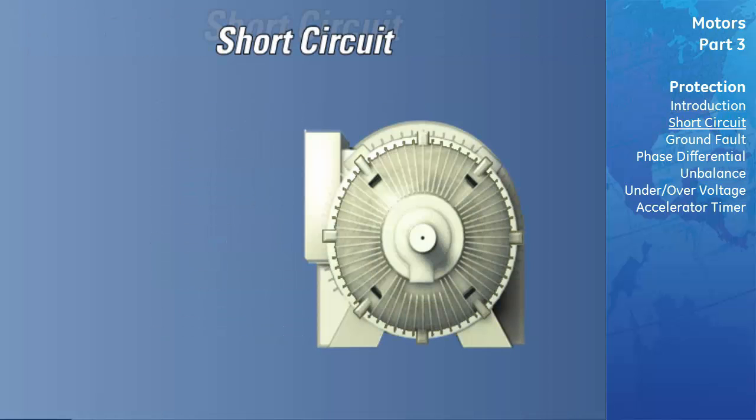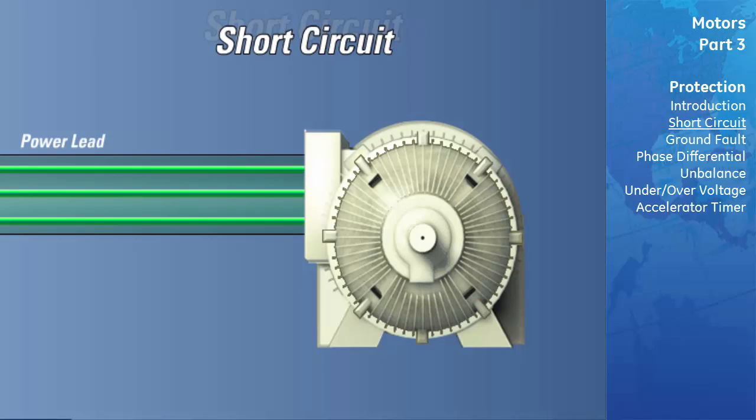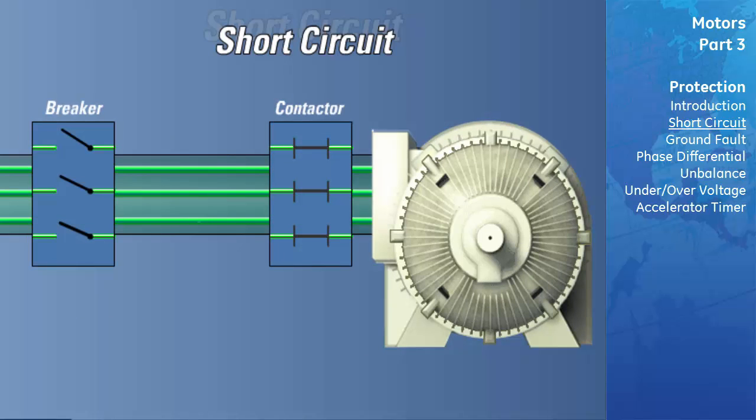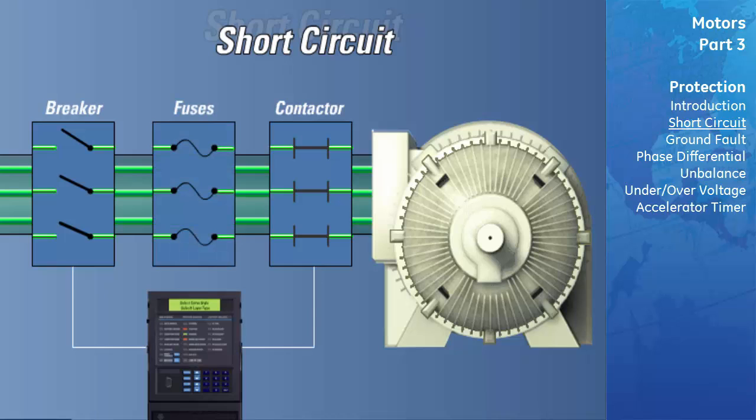Short circuit protection. The short circuit element provides protection for excessively high overcurrent faults. Phase-to-phase and phase-to-ground faults are common types of short circuits. The short circuit trip element is coordinated with external upstream fuses such that the element will operate first. When a motor starts, the starting current, which is typically six times the full load current rating of the motor, has asymmetrical components.